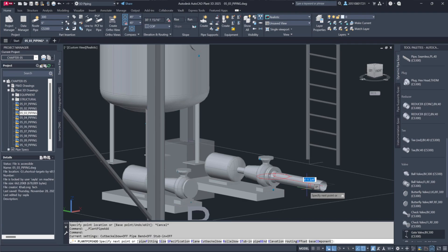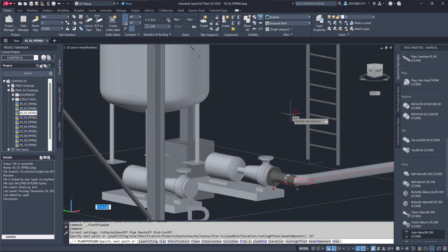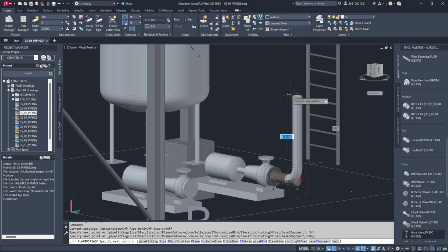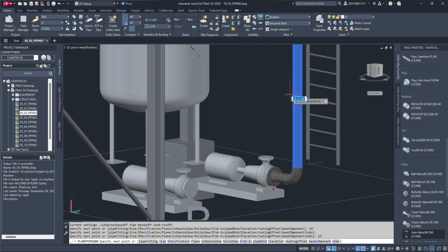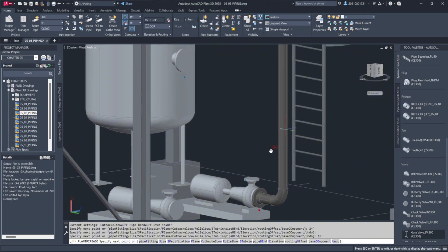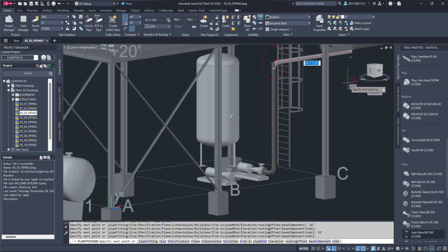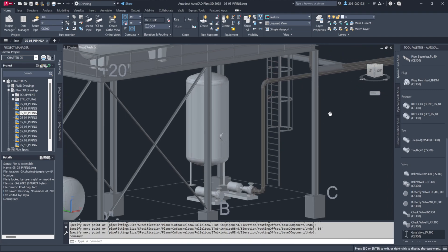Dynamic input allows precise dimensioning during piping. For example, you can run a horizontal pipe 24 inches, adjust the compass using Ctrl+right-click to switch direction, and then create a vertical run of 15 feet. The compass tool ensures proper alignment for subsequent connections, such as a 30-foot horizontal extension.